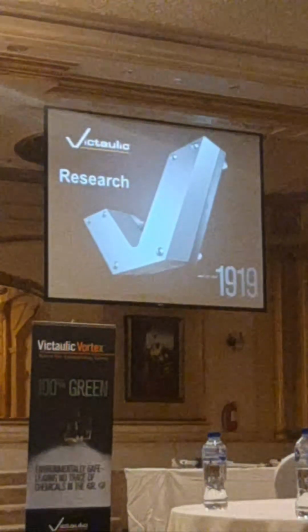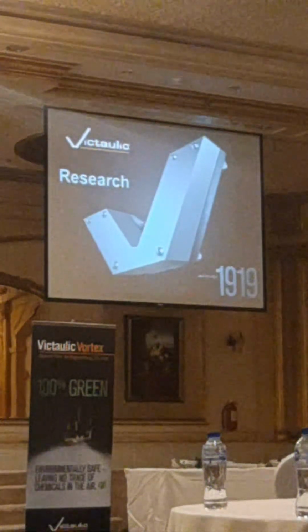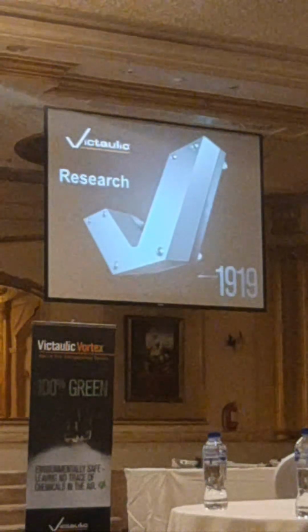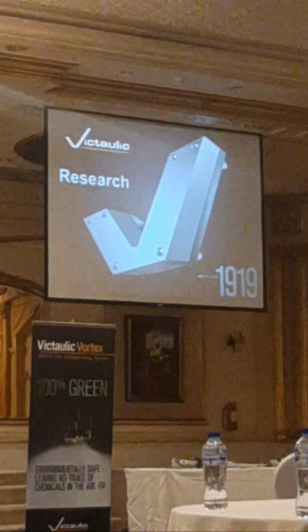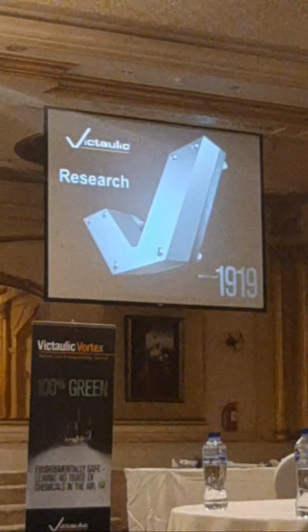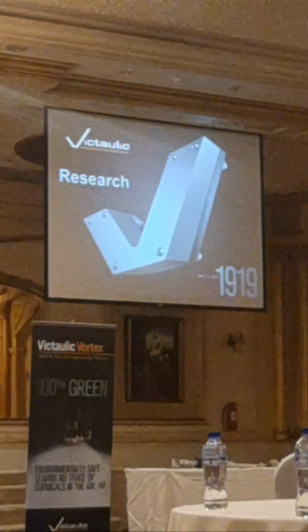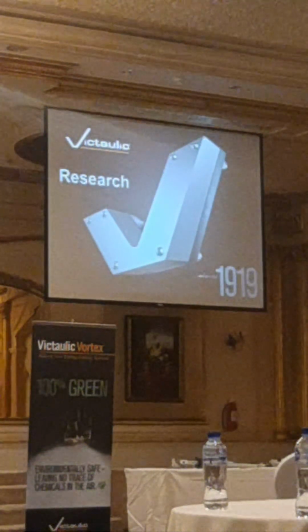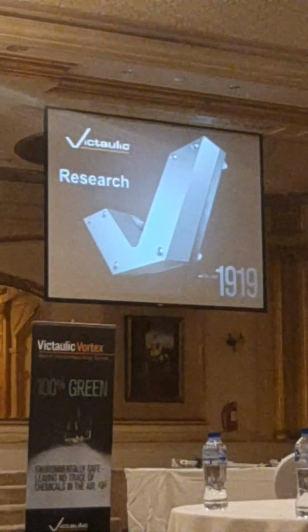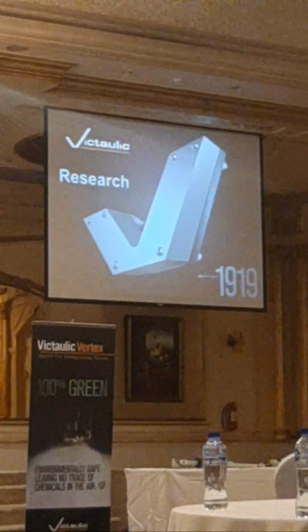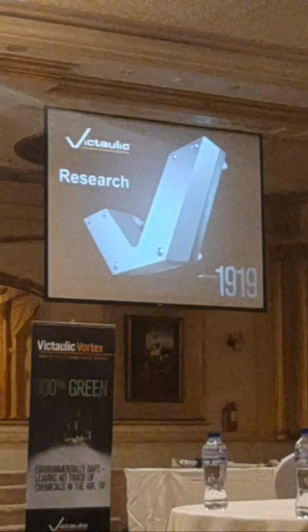The normal ventilation that you have running - if the fire starts, any sort of external ventilation would need to be shut down. Similar to a gas system, you don't want to add any oxygen during the discharge, and also any extraction ductwork needs to be closed off.